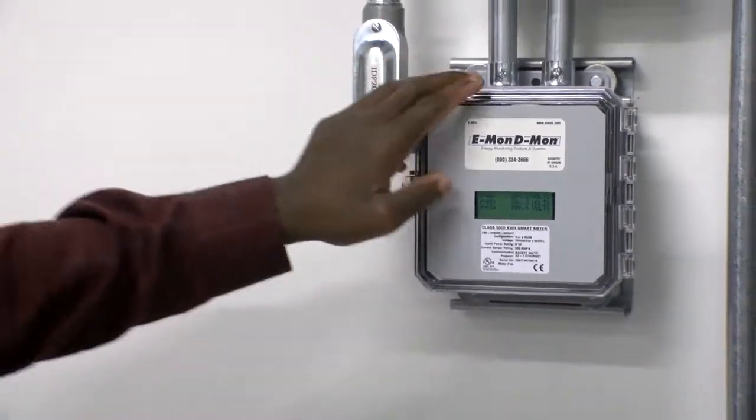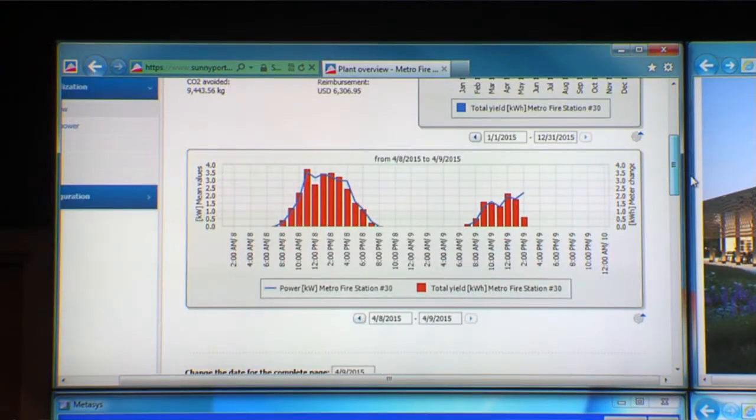General Services identified a relatively new technology — advanced electrical sub-metering — to detect energy usage for a more complete picture of critical mechanical systems at Bellevue Library. A smart meter was attached to the electrical panels to monitor the largest energy consumers, such as the HVAC, hot water, and lighting systems. The smart meter recorded, in real time, minute by minute, the power draw for each of these systems.